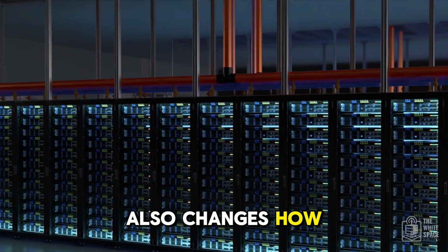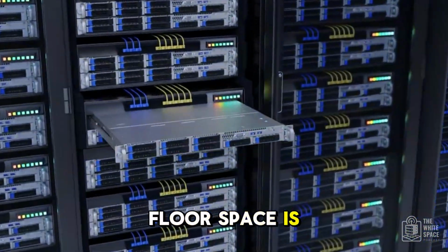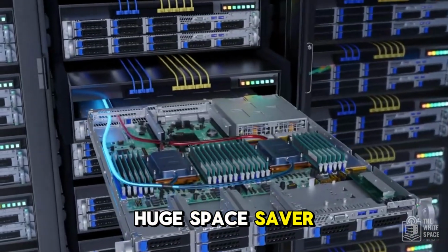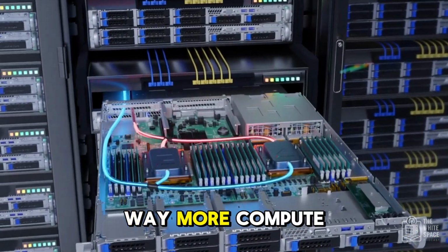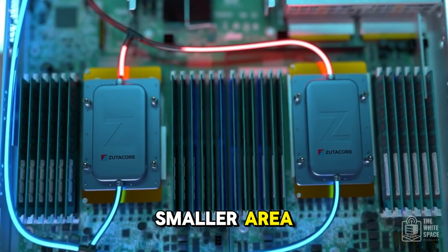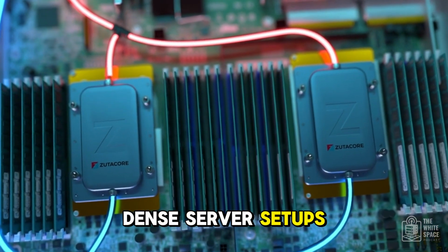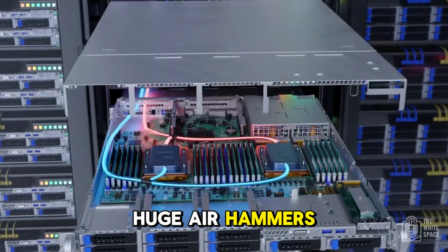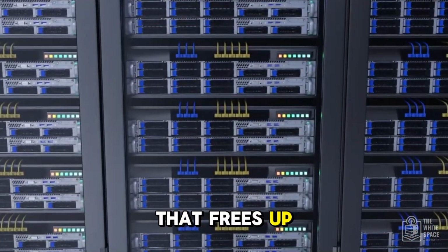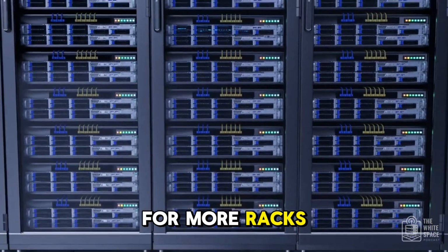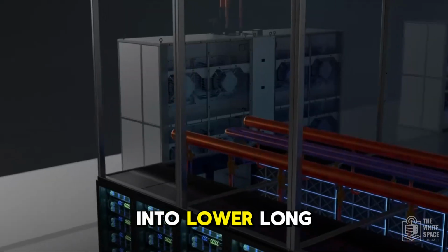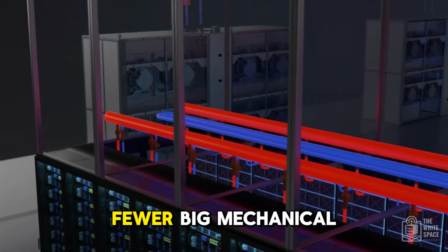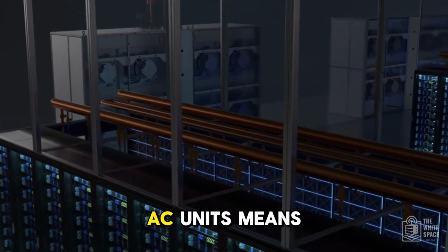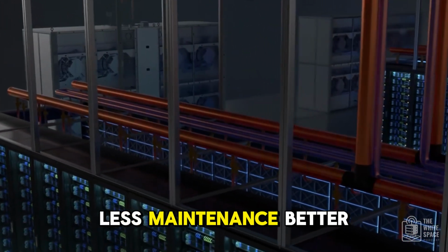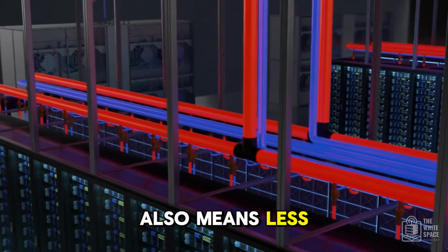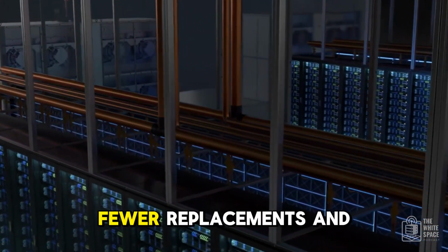I bet it also changes how you use space in the data center. Floor space is always tight. Oh, it's a huge space saver. Liquid cooling lets you pack way more compute power into a smaller area, supports those really dense server setups. Plus, you don't need as many huge air handlers or bulky ductwork. That frees up valuable white space for more racks, more IT equipment, and this feeds into lower long-term operating costs too. Fewer big mechanical parts like fans and AC units means less wear and tear, less maintenance. Better cooling also means less hardware failure from heat stress, fewer replacements.